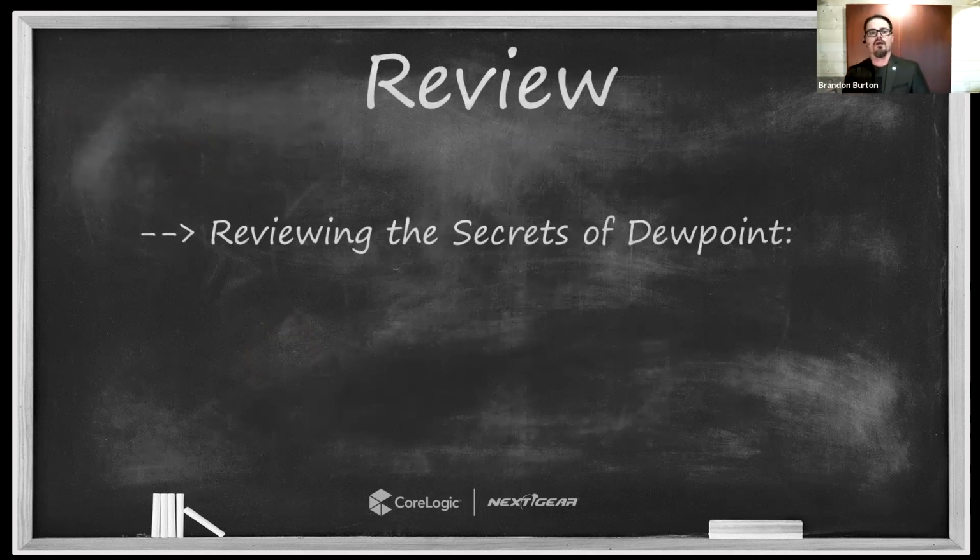Okay, so a couple of things here in closing and in review. First and foremost, the most important thing I want to drive home about dew point is that it's a tool, a metric that you need to use. We have lots of documentation that we do simply because that's what's on the form. The form asks me to record temperature and humidity and grains per pound in the affected area and outside, and things like this. That's well and good, and there's purposes for that documentation, and we get lots of value out of it. But at least understand dew point. When you're calculating your indoor readings, especially where you're affected, and that's where they're going to be highest, at least calculate that dew point.